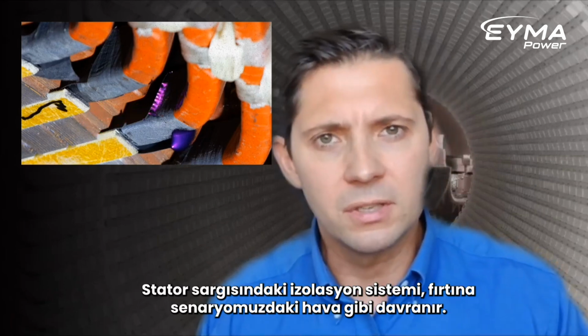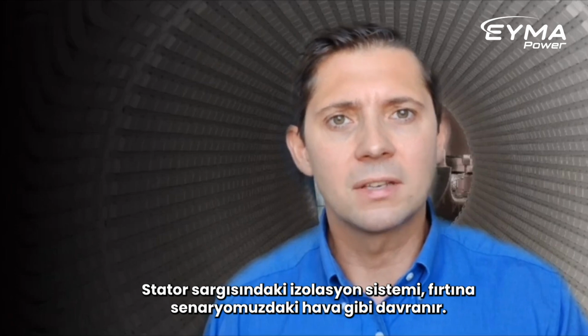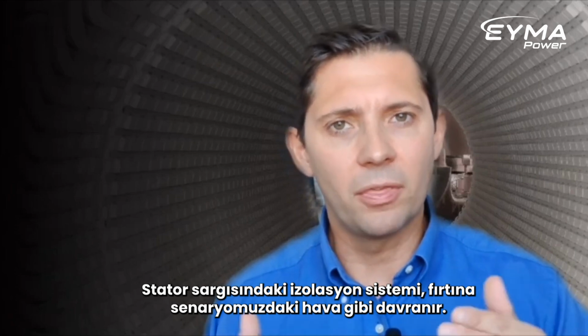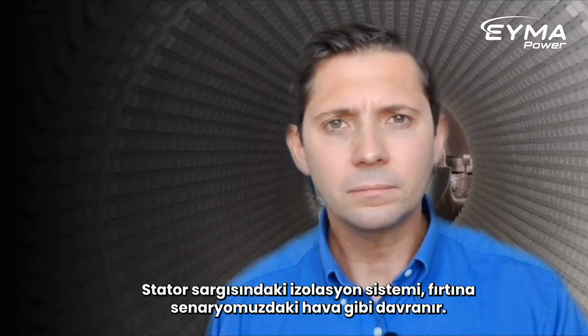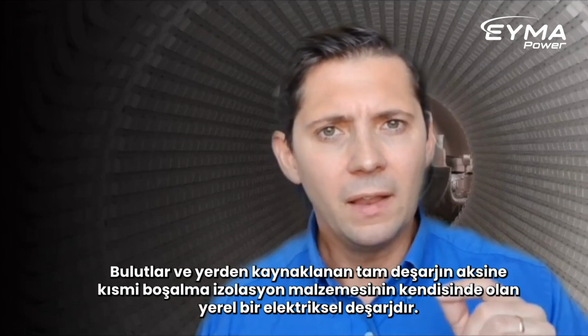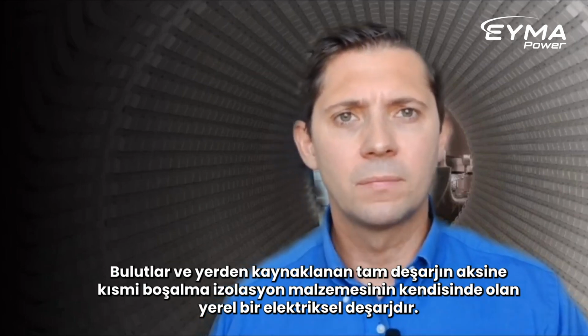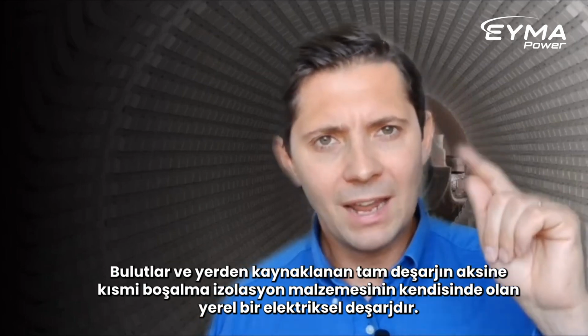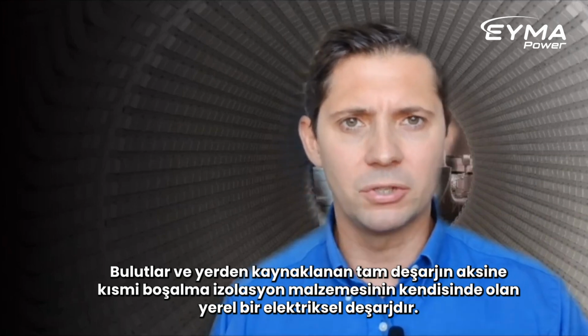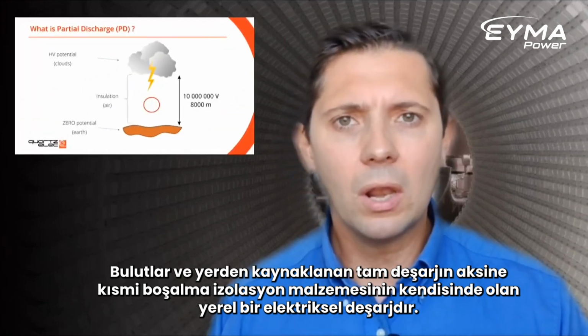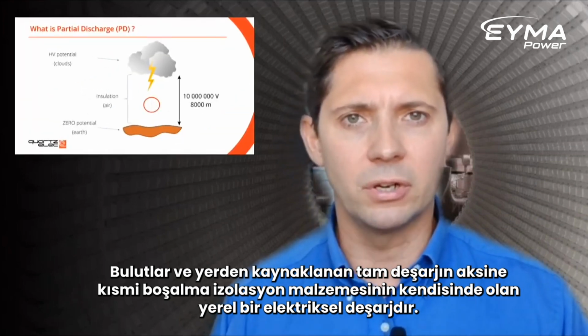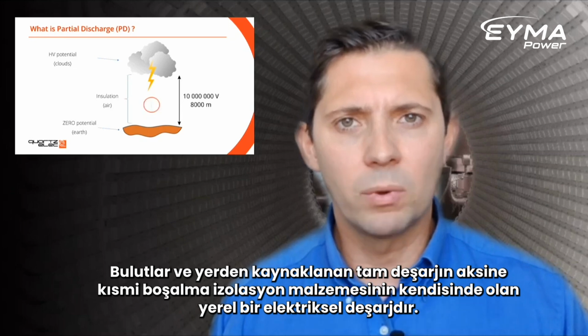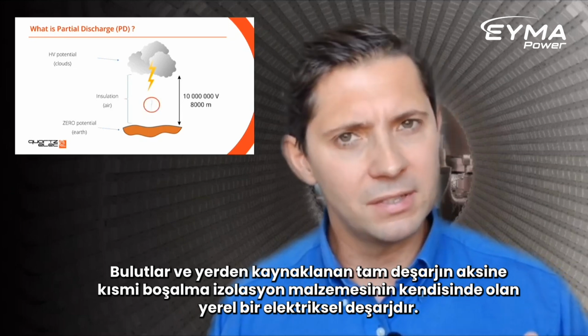The insulation system in the stator winding acts like the air in our thunderstorm scenario. However, unlike a full discharge that spans from the clouds to the ground, the partial discharge is a localized electrical discharge that occurs within the insulation material itself.